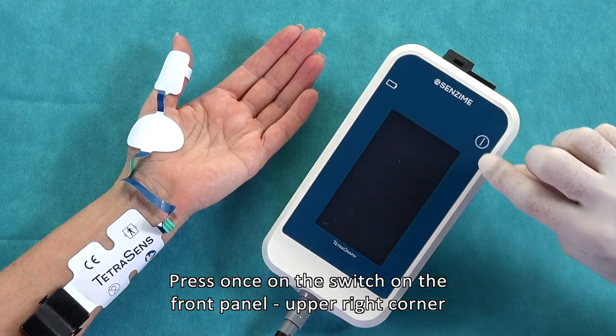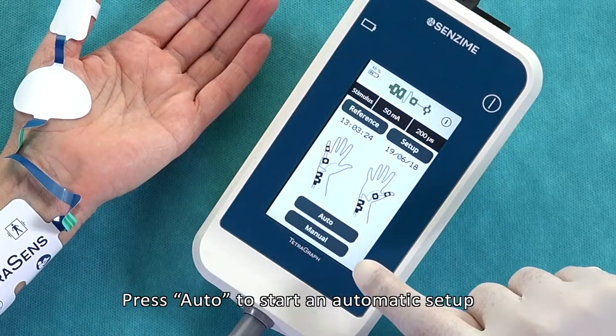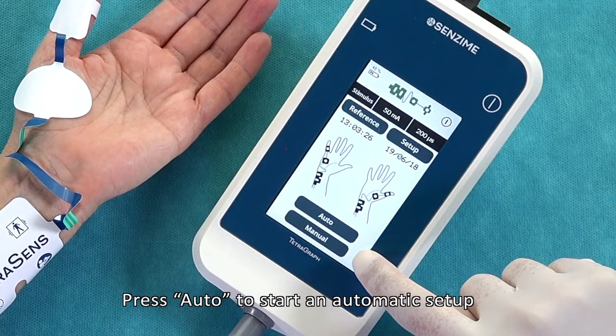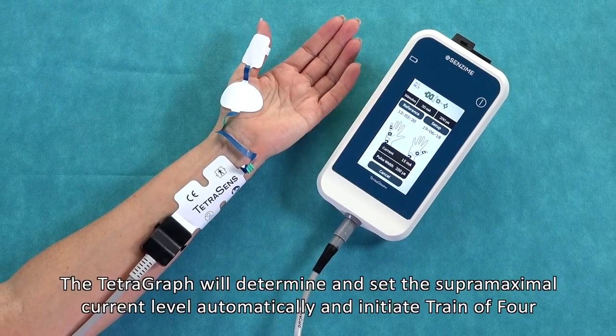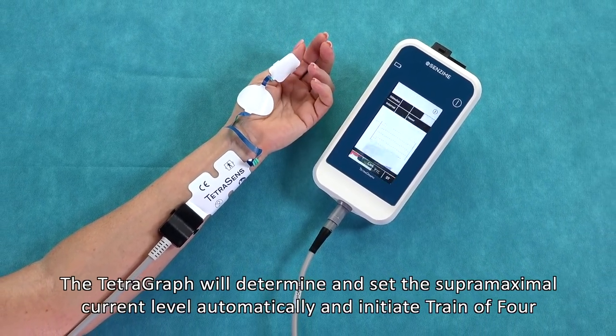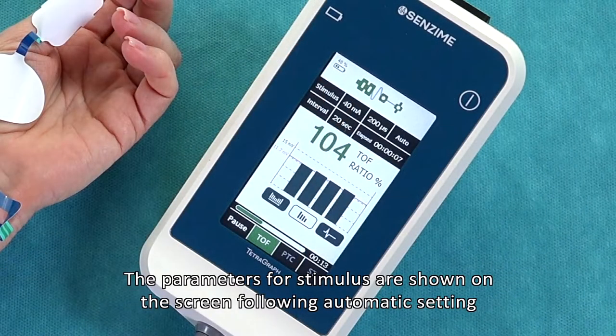Press once on the switch on the front panel, upper right-hand corner. Press auto to start an automatic setup. The TetraGraph will determine and set the supramaximal current level automatically and initiate train of four. The parameters for stimulus are shown on the screen following automatic setting.